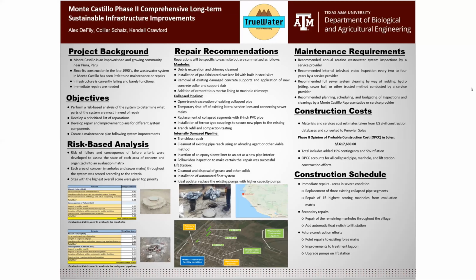For the lift station, recent repairs had been made by local contractors, but we recommended that the wet well be cleaned out and that all of the grease, sludge, and other solids be disposed of. We also recommended that an automated float system be added to the lift station to make the operations run smoother, because right now everything is running either manually or with a really old system. And ideally, in the next few years, the lift station would receive two new pumps that have a greater capacity.